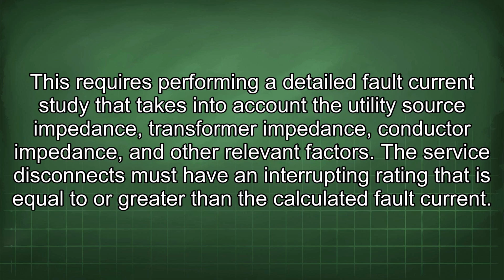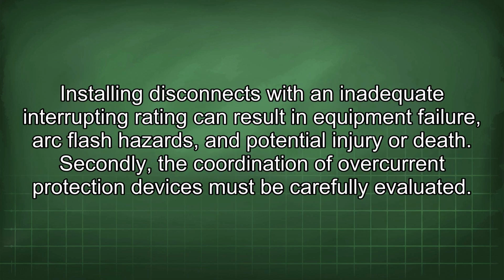This requires performing a detailed fault current study that takes into account the utility source impedance, transformer impedance, conductor impedance, and other relevant factors. The service disconnects must have an interrupting rating that is equal to or greater than the calculated fault current. Installing disconnects with an inadequate interrupting rating can result in equipment failure, arc flash hazards, and potential injury or death.